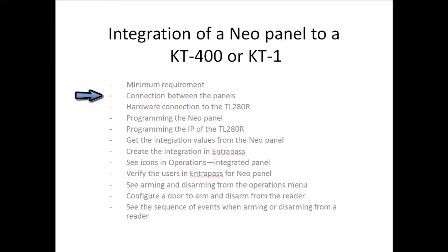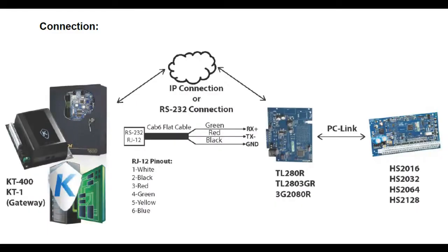Now let's take a look at the connection between the panels. From the right side, you can see the NeoPanel connects to the TL280R, and then the TL280R over Ethernet will communicate to the KT400, which then communicates with the EntraPass software. You have to remember that you'll need to use a static IP address on the KT400 or the KT1.